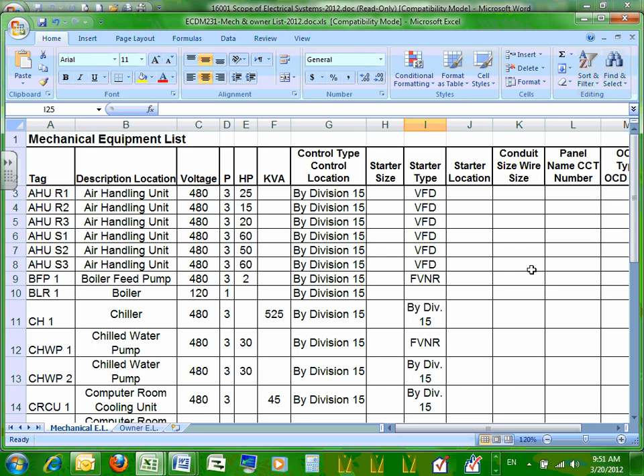VFDs in my world are by electrical. That's my world. Different offices do different things, and different offices do different things within the same office. But in my world, the VFD should be specified by electrical. There's too much harmonic issues to deal with. And in many shops, they say, well, it's simpler to let the mechanical require the VFD because then it kind of serves that motor. Well, there's really nothing magic about what that motor is. I mean, the motor has to be compatible with the VFD. So that's all the mechanicals need to say, is that it's compatible with the VFD.